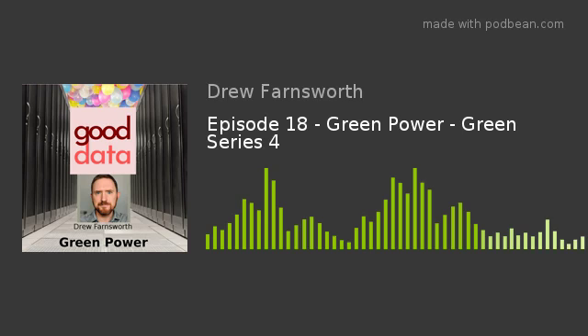There's the issue of the efficiency of the actual transformers. Transformers in a UPS or anywhere work better when they are loaded close to 80%. That's just the way that the efficiency curve on a transformer works, because it's an inductive load, because it basically has magnetic properties within that transformer that allow power to change from one voltage to another. There are no wires that are connecting. It's a waveform that is induced on the load side from the line side. And that requires, it's basically electromagnetism, to create that vibration, the oscillation, to create that 60 hertz wave on the load side.